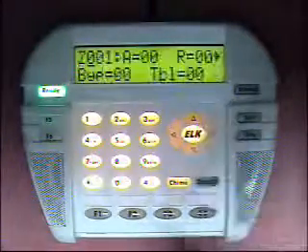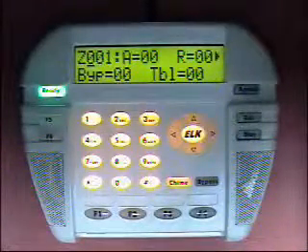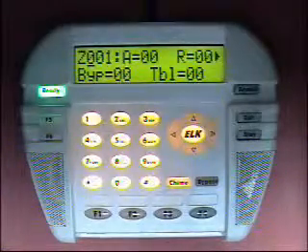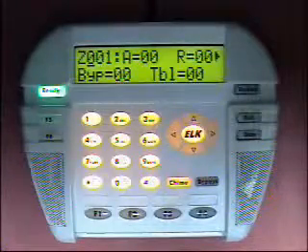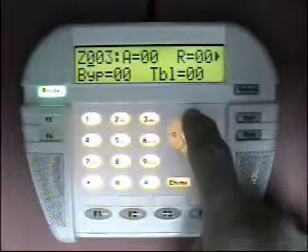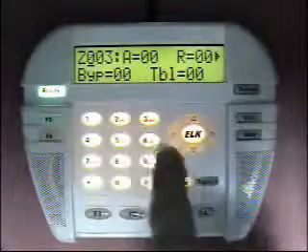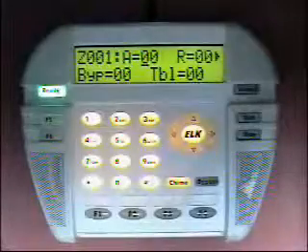Press the right arrow to enter zone reporting codes. One thing to keep in mind is each zone in the system has its own set of reporting codes, so you can customize each zone to what it will transmit, or disable it so it will not transmit at all. We're indicating zone 1; using the up or down arrow we can go to any zone, or simply type in the zone. I'll go back to zone 1 by typing 001.